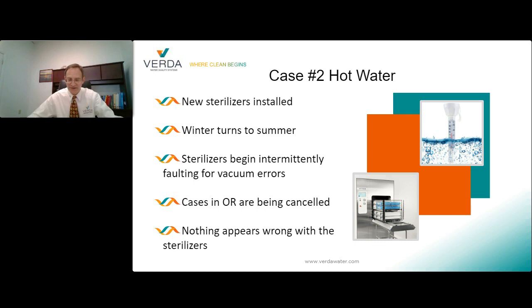That's the short-term fix. But operating the vacuum pumps without adequate liquid cooling was reducing, one, the vacuum capacity of the pumps themselves, and two, stressing the pumps, so they were likely to have to be replaced again in the near future. So the long-term solution was to provide chilled water to the sterilizers, meant to cool the vacuum pumps, and separate this water from other utility water used in the SPS. This chilled water was recirculated locally to minimize the gallon per minute consumption of the chilled water in the department.